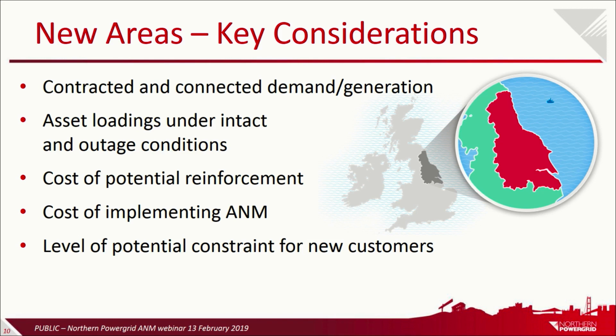We need to bear in mind the cost of a reinforcement solution. So when Ian was talking earlier, he mentioned that the time to use ANM is when the cost of the reinforcement works are disproportionately high compared with the cost of ANM. So we need to understand both the cost of the reinforcement and the cost of implementing ANM, and we need to understand generally the level of curtailment that customers would be suffering and what that potential cost is and how that all comes into the mix to determine whether ANM is a good value solution. And so the level of potential constraints that those new customers are going to see are really important. If the constraints are too severe, customers aren't going to sign up for it.